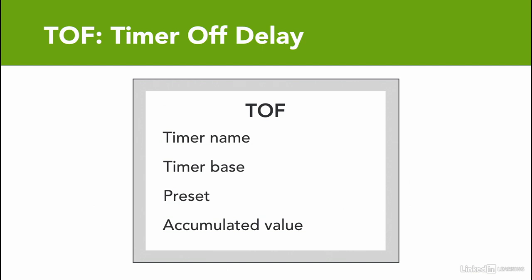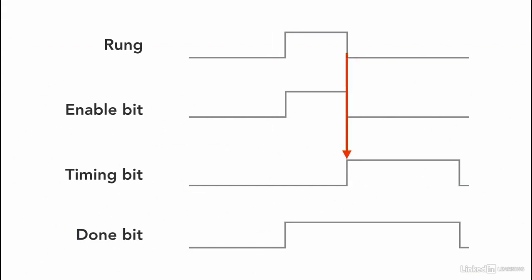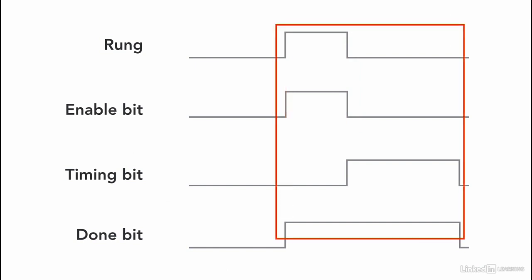The timer off delay works in a little bit different format. The enable bit is true when the rung is true. The timer starts timing when the rung goes to false. And done bit is on as soon as the rung is true and stays on until the timer done timing.